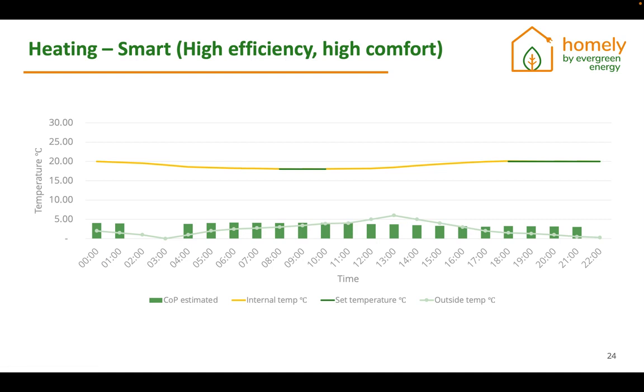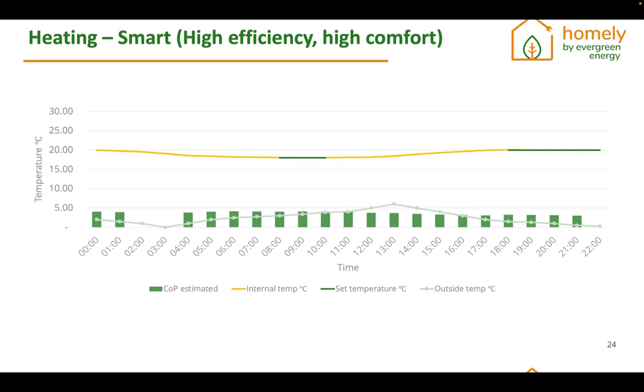Homely will make these decisions for the customer, and they just need to trust that it is doing the right thing. Then throughout the day, what we can see here is that the internal temperature starts slowly rising to the evening set point. So the heat pump is not working super hard, but it's gradually raising the flow temperatures so that it can achieve the desired set point for the evening. This is where smart mode is going to be running almost continuously throughout the day with low flow temperatures, achieving high efficiencies for the customer and the lowest cost. So even though the heat pump runs for longer, because you're achieving much greater efficiencies than in the other scenario, this will actually help you achieve the desired outcome of comfort and efficiency.